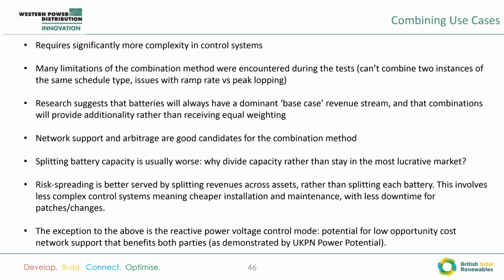The base case is very important. I think that trying to put together an investable battery based off of, let's say, relying on 4 or 5 different use cases, some of which may change as the network demands change, I don't believe that investors will go for that. I think what you need is a base case that says this is the standard thing that the battery will be doing, but here's the additionality we can get by putting it here. We can get these contracts, or potentially get longer revenues if it's doing network support in an area that's expected to delay it for 5 or 10 years. That is of great interest to investors.